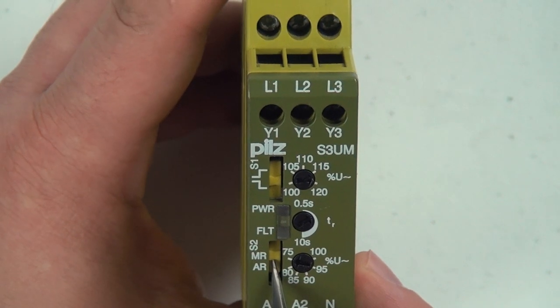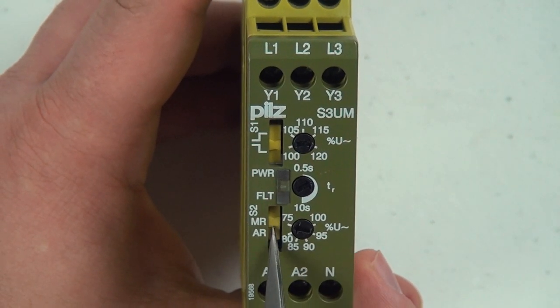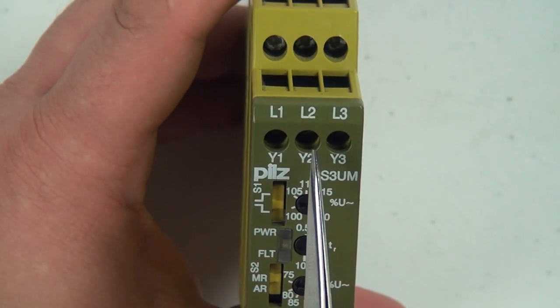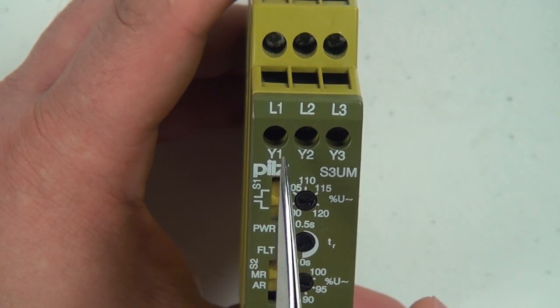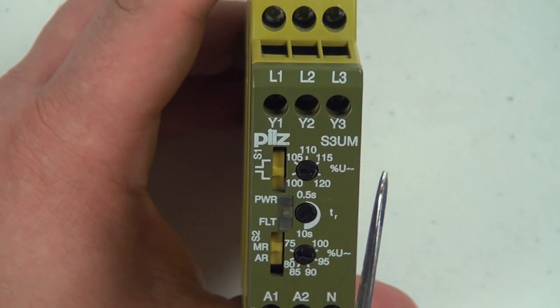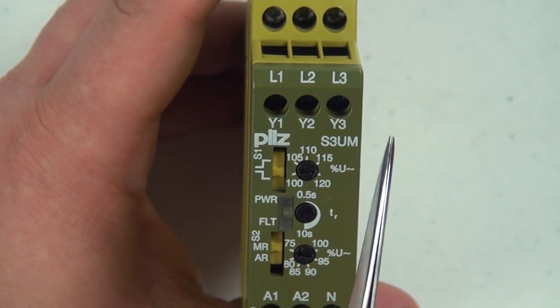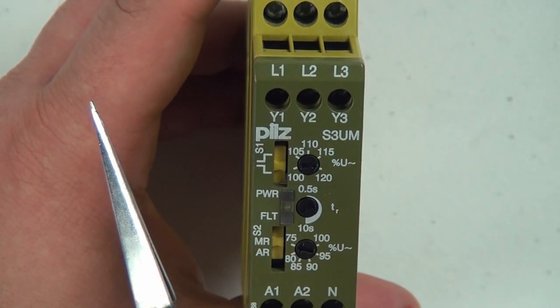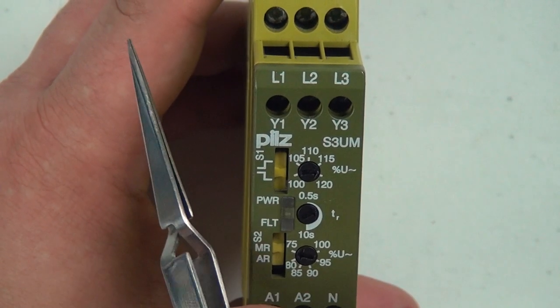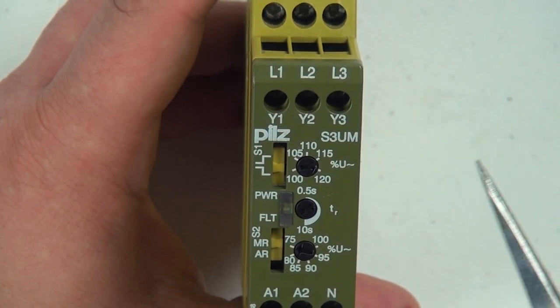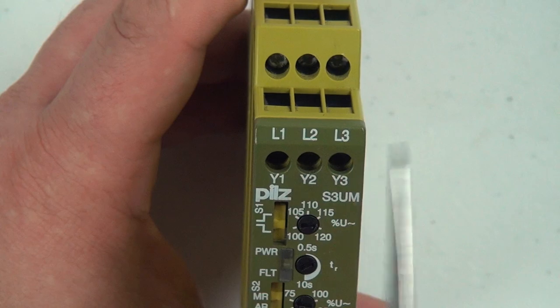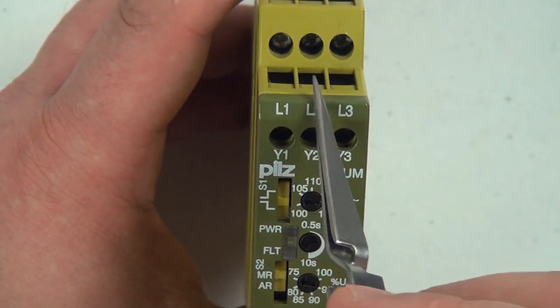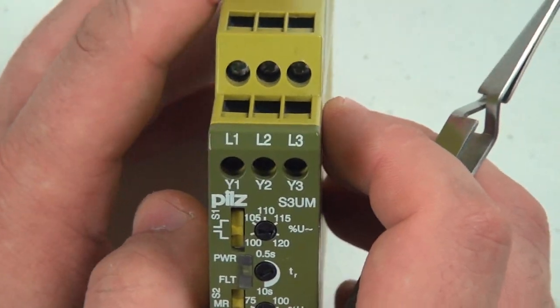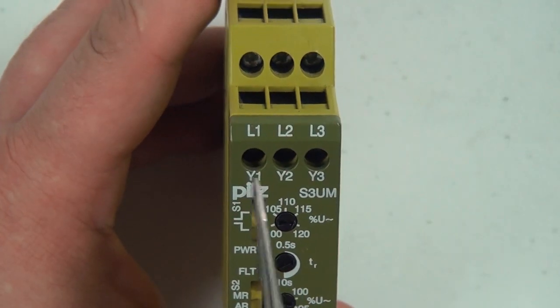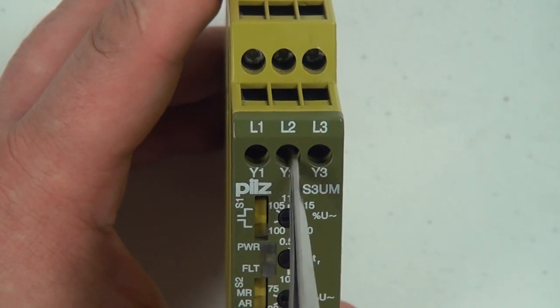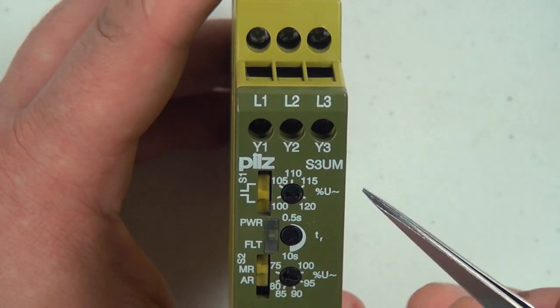If you have manual reset, which would be this pushed up, the relay has to see a momentary connection between Y1 and Y2 to let the relay know that it's okay to transition from the faulted state to the not faulted state. And so if you tie these two together momentarily with a push button, and this is going to be done separately somewhere on the outside of the equipment, it would be the reset button that you would press.